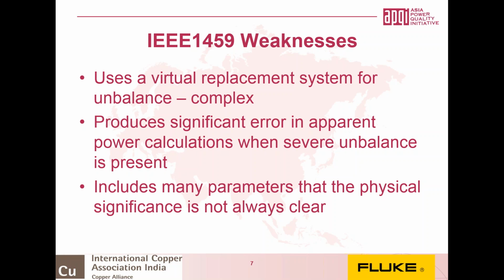The biggest problem, of course, is that it produces some errors in apparent power calculations when severe unbalance is present, because the unbalance is only allowable within a certain range. And finally, although the system of the IEEE 1459 develops lots of different values, sometimes the physical significance of those values is not necessarily that clear. They are predominantly used for calculations or sub-calculations through the system, which is helpful to a certain extent, but in terms of practically applying this in the field, that becomes difficult.